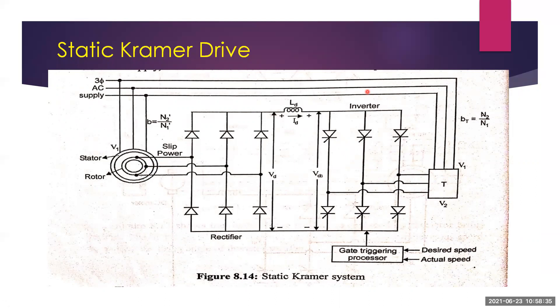Instead of wasting the slip power in the rotor circuit resistance, it can be converted into AC and fed back to the supply by using a transformer. This method is called the static Kramer drive. The slip power can flow in only one direction. This circuit diagram shows the static Kramer drive for speed control of a slip ring induction motor.